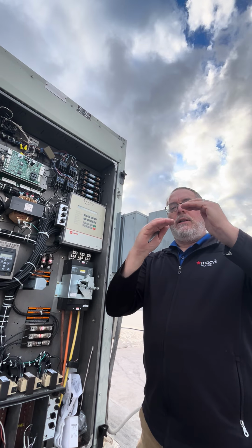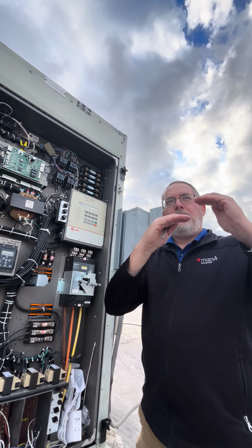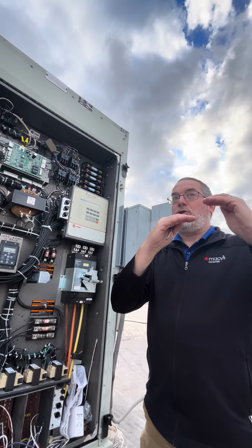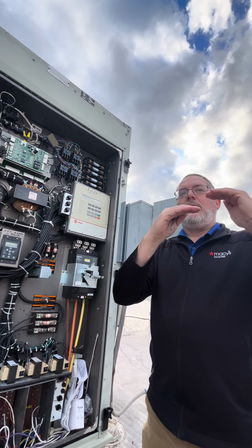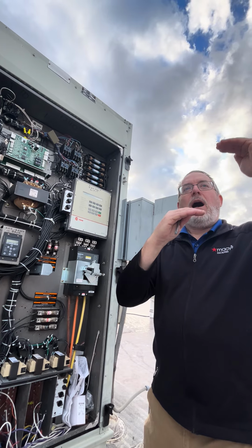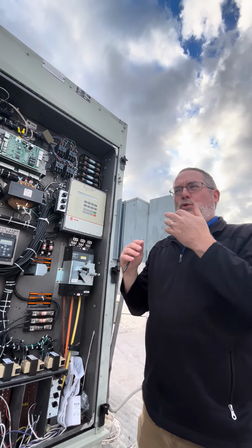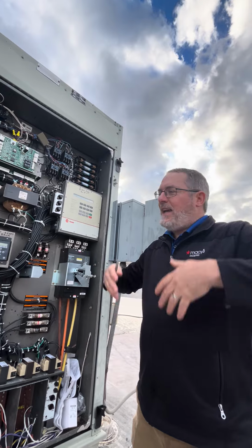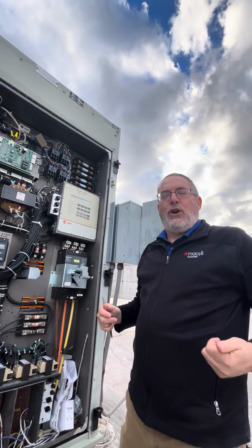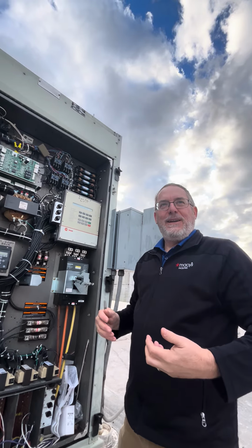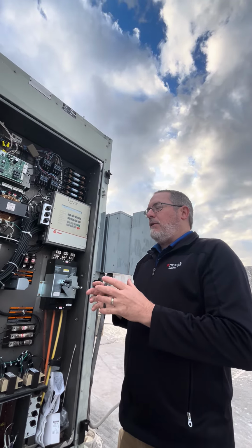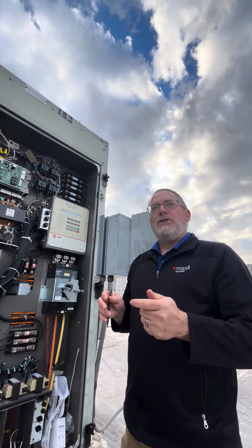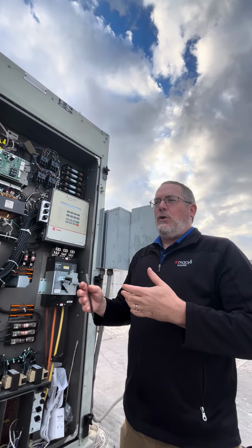But I release cooling here, get a good cold discharge, cold deck, and then I let my VFD go up beyond that. So we try not to just get in the gas and flood the store and then turn it off. Right, flood the store and turn it off. A lot of our stores have that older strategy, and you don't. It is what it is.